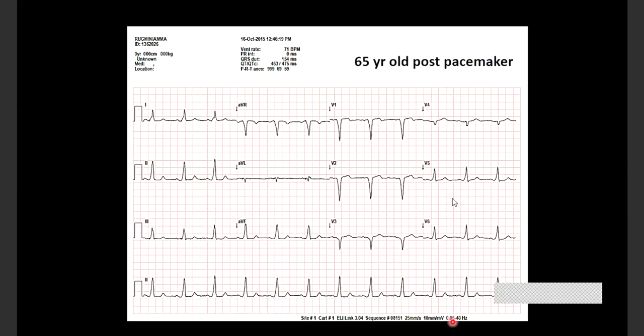The reason they've kept the high pass filter at 0.05 is that anything less than 0.05 is a very low frequency signal, and the signal which causes this interference is usually the breathing pattern of the patient. It's a low frequency signal. So if your filter setting is really low, then you'll have baseline artifact. The patient's breathing will create an artifact. You'll have an undulated baseline. You'll not have a static baseline.